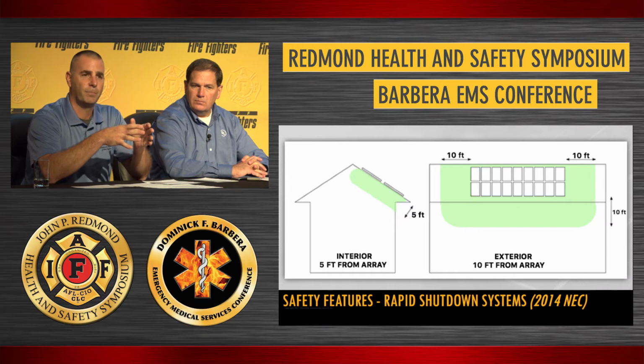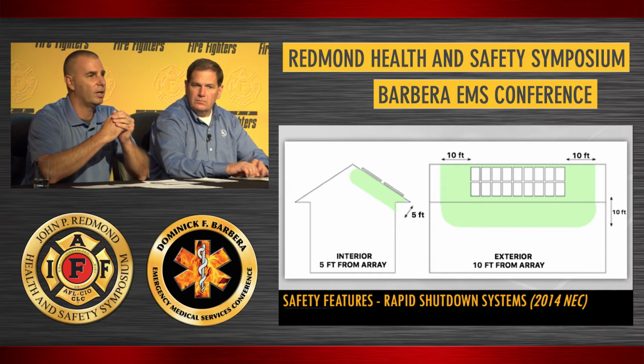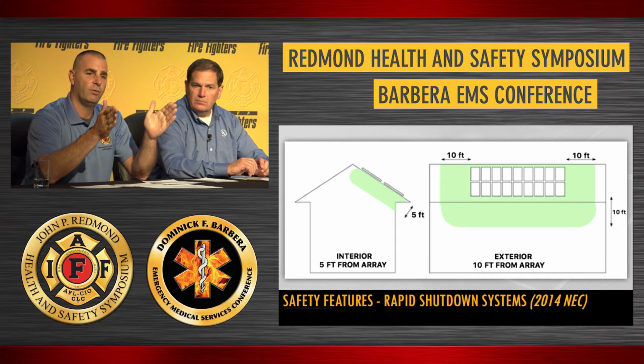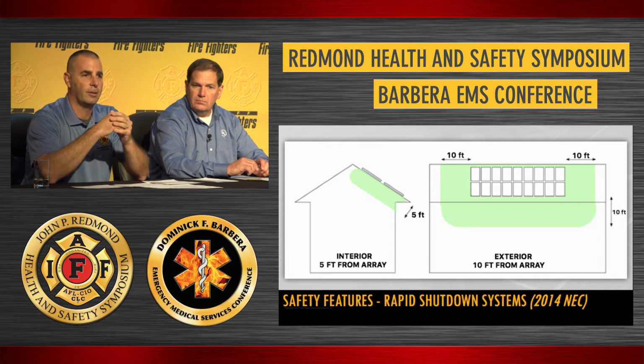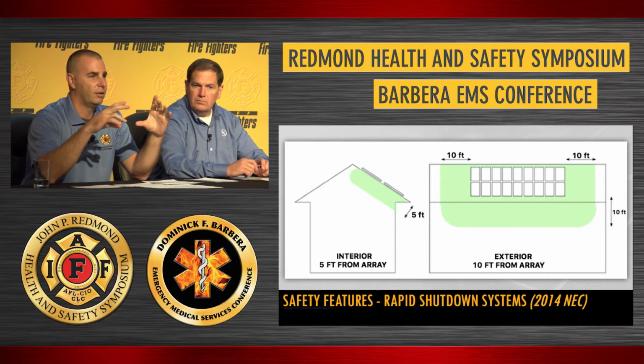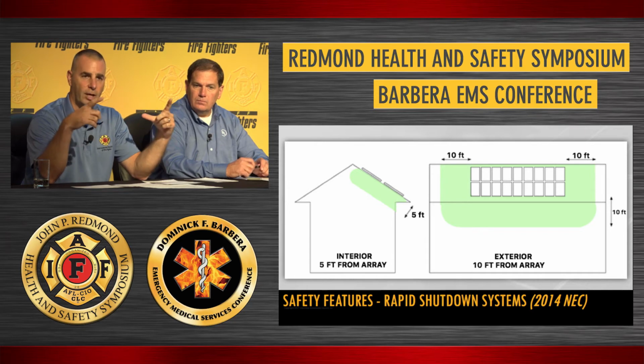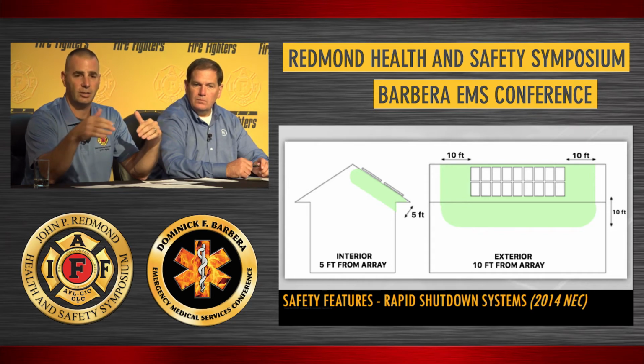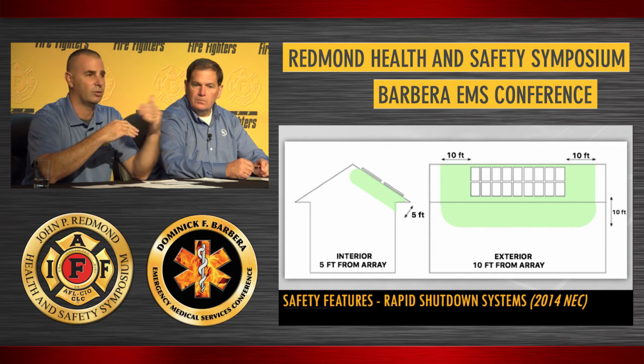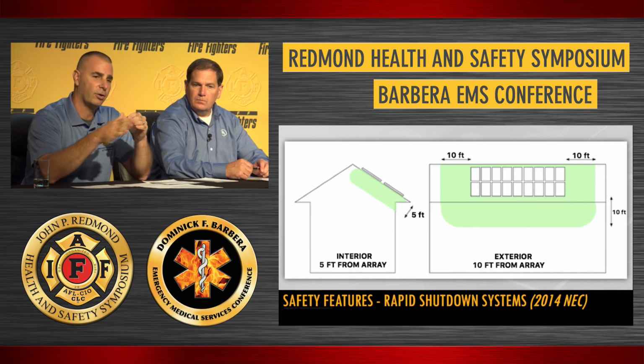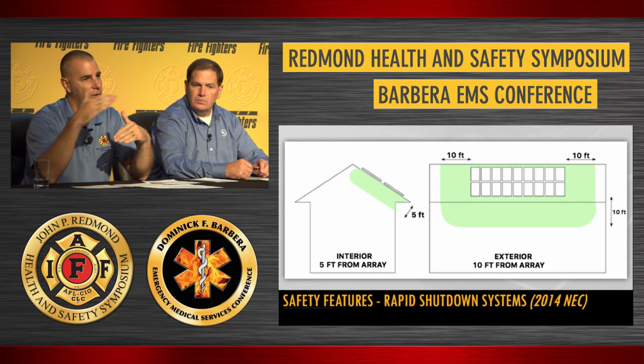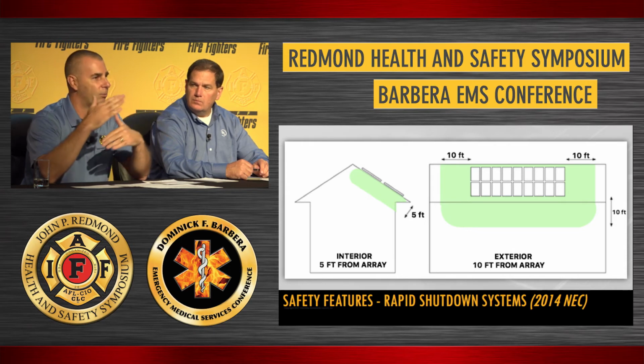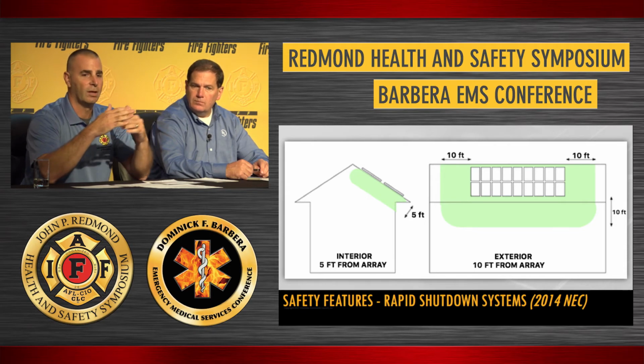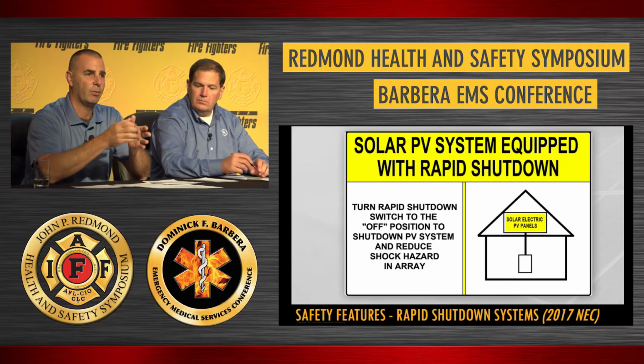What that means for us is if you look at the array on the right side of the house, it has a 10-foot boundary around the array. Within that boundary, the voltages remain at the full level of the array - up to 600 volts for residential and up to 1,000 for commercial. On the interior, it shows a 5-foot boundary, so from the array to 5 feet will still be full potential energy. This is the 2014 code. In 2017, they did some adapting to the code and came up with a new sticker.